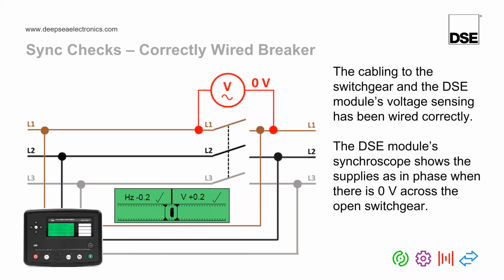So here is an example of a correctly wired breaker. In this case, you can see that on the left-hand side the DeepSea module is measuring L1, L2, L3. At the breaker, it's L1, L2, L3. And at the other side, it's L1, L2, L3. And when the DeepSea module synchroscope is showing the 2 supplies in sync, we are seeing 0 volts across the open breaker. Perfect. Everything is okay.